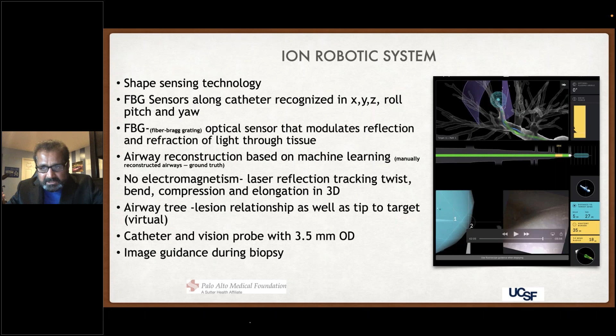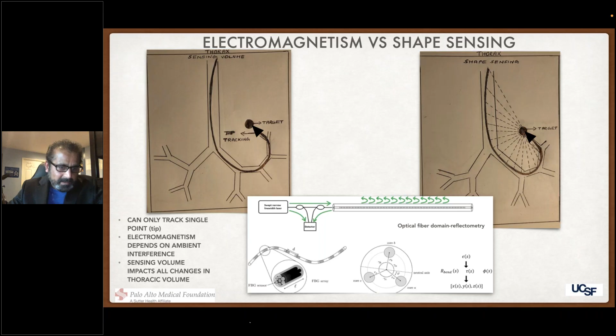target airway. But the system also measures, if you look at the right top corner, the catheter stress. If there is excessive stress with the tip bend radius of less than 20, the system is actually telling you that you're causing too much airway to nodule relationship change, and therefore you can retract the catheter and re-navigate and get a better acquisition. So the system gives you better feedback of the 2 big problems that are persistent, the CT to body divergence and the airway to nodule relationship. It gives you enough feedback so you can actually change things around and get better acquisition.